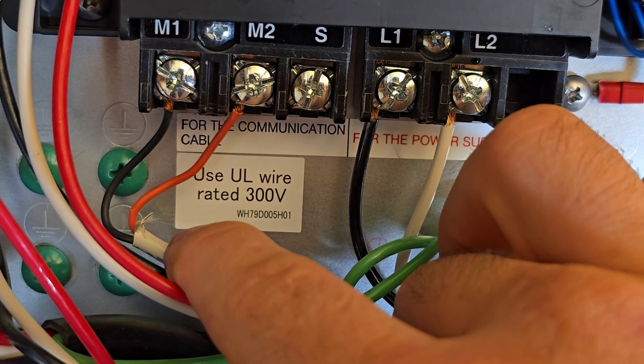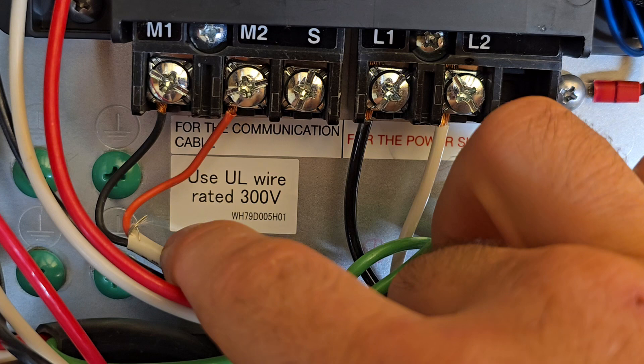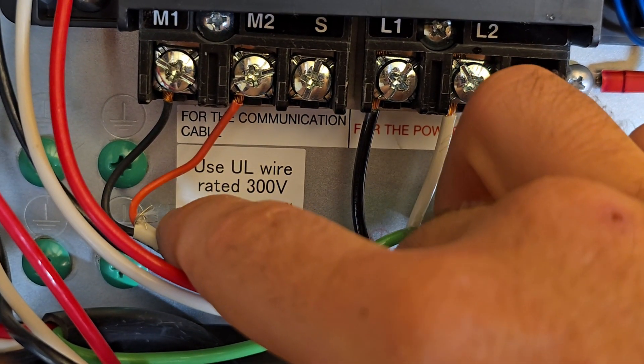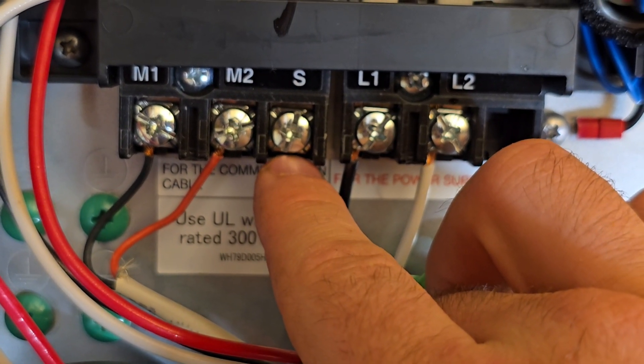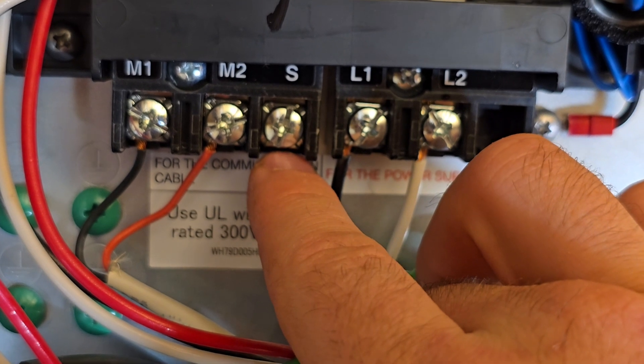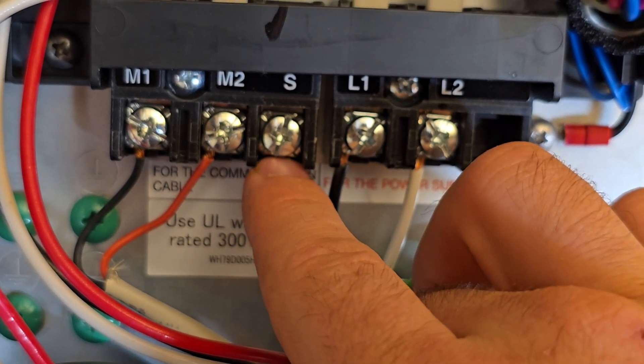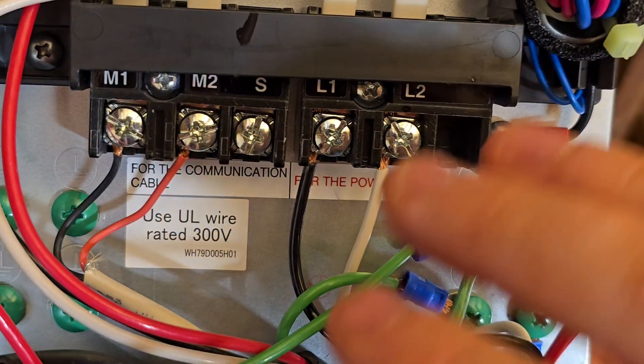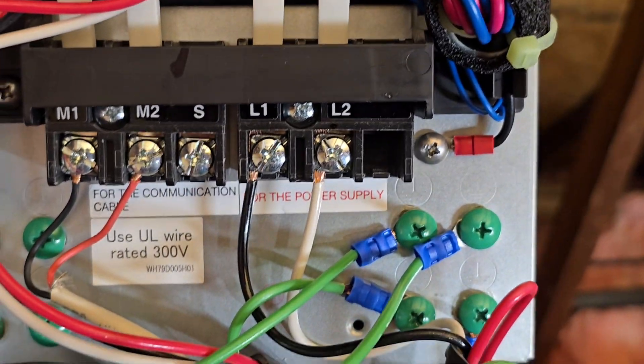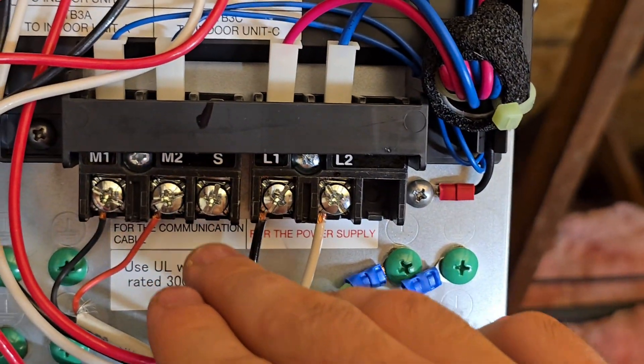So it doesn't matter which end you want it hooked up to, but your shield should only be hooked up to one side – either the compressor side or the branch box side. It doesn't matter which, for either branch box if you have multiple in the system. I just like having everything hooked up to the compressor.